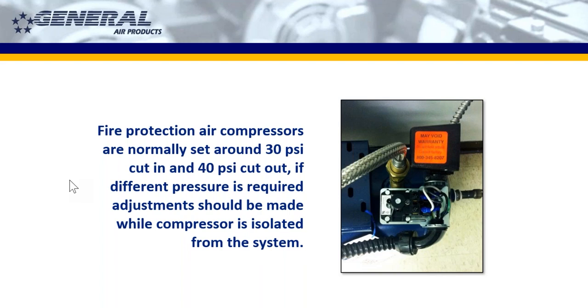But for the pressure switch adjustment, again, make sure you're not adjusting the differential screw. You want to make sure that the differential doesn't go any lower than what it's preset for. In this instance, the differential is 10 PSI between the 30 and 40 PSI cut out. That's the lowest. We always preset these at the lowest differential that they could possibly be at. You can increase the differential in some instances where that's necessary.